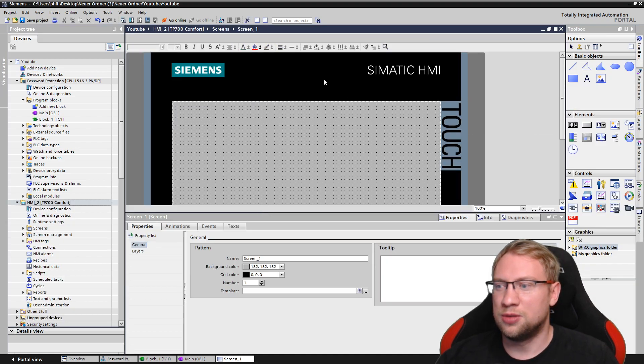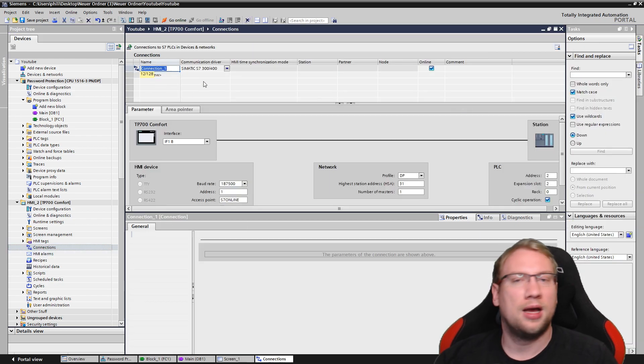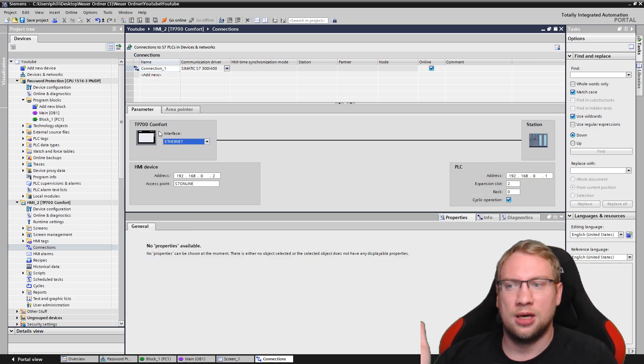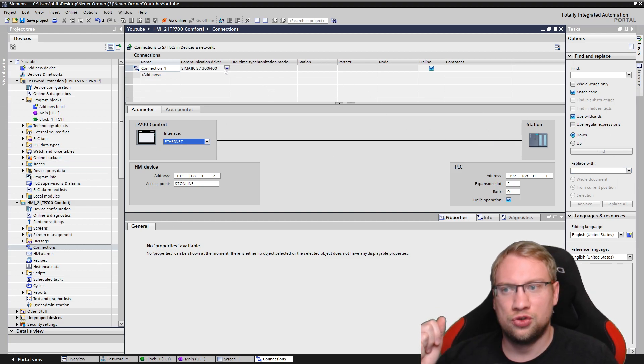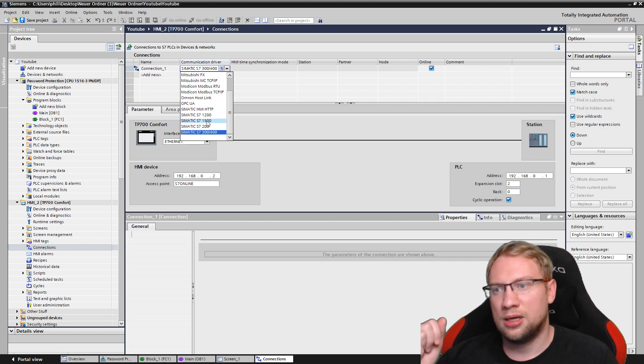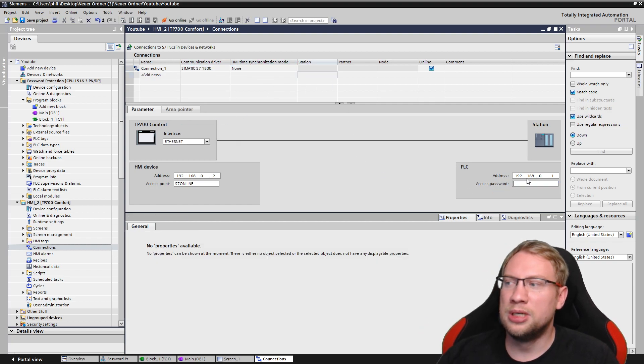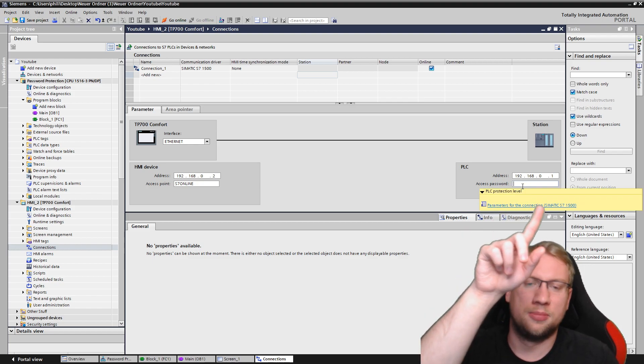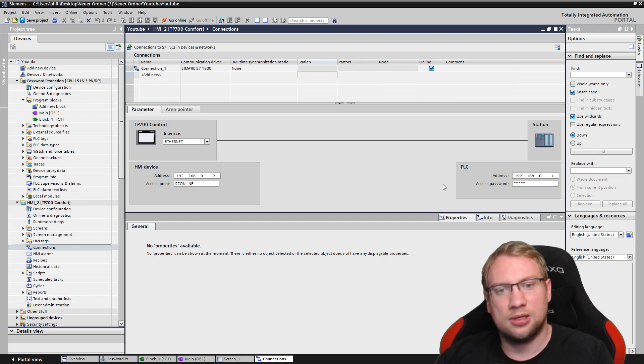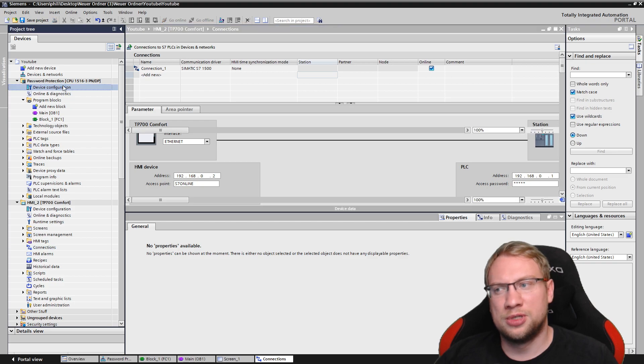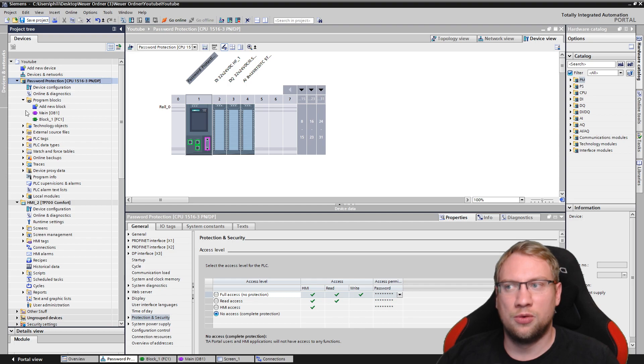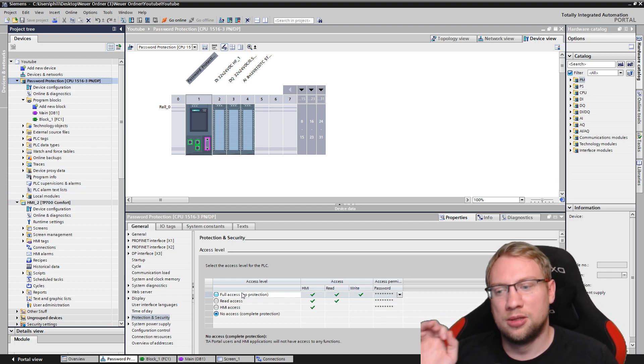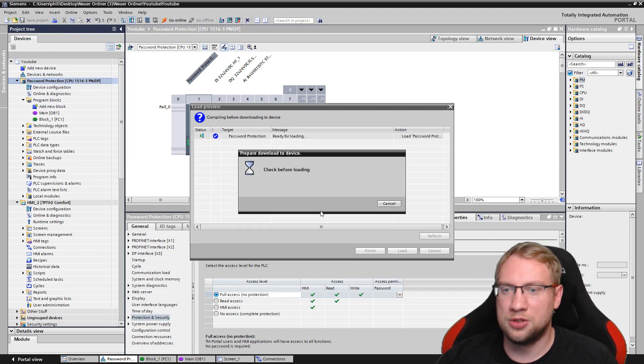So your HMI will also need a password, which is set like this. Here we have the HMI, right? And we have the so-called connections, right? I have explained that in another video, but we have the connections, which is basically communicating a PLC to a HMI. And I've got this. And here we go. We will need to set an access password, right? This is the password I just had for the, I just typed in HMI access, right? Those are the protection levels here, right? This is how you can protect your full program. Now full protection is on, so no one can access my stuff anymore. The problem right now is I forget passwords, so I don't want that. Let me turn that off. Let me download it.